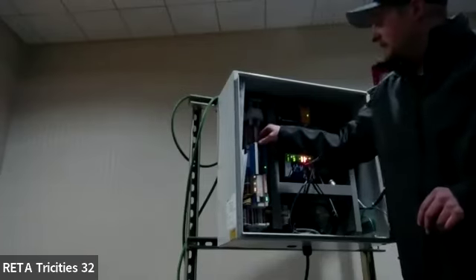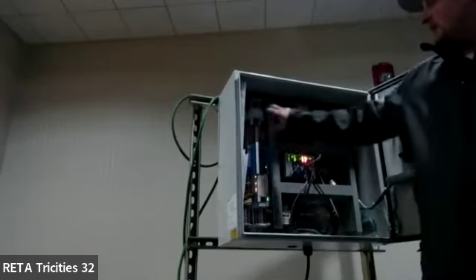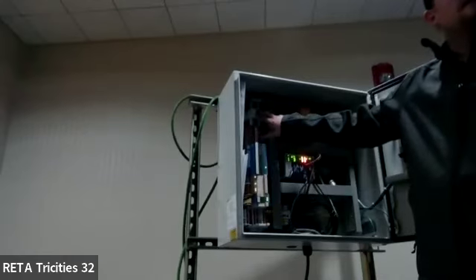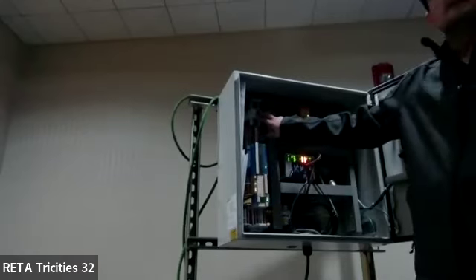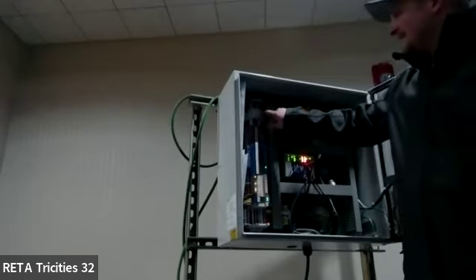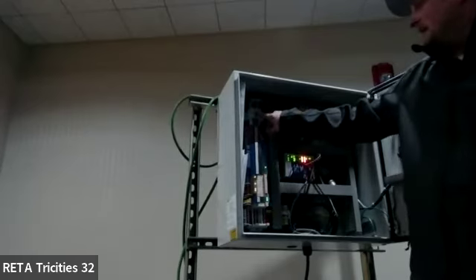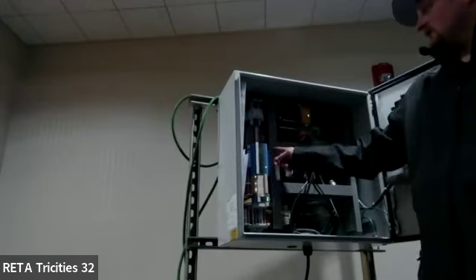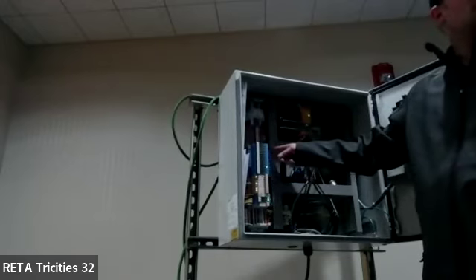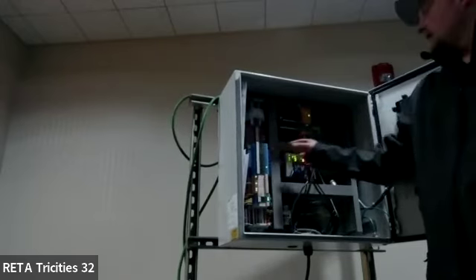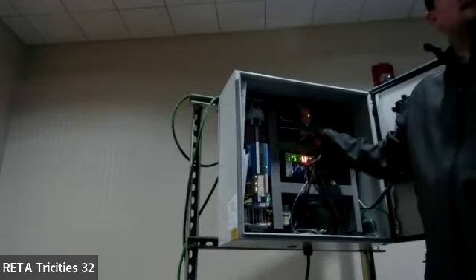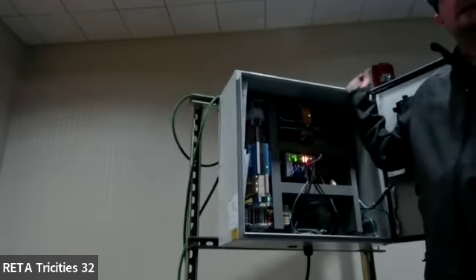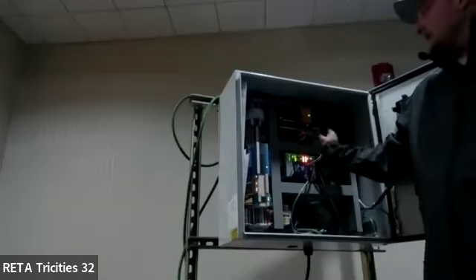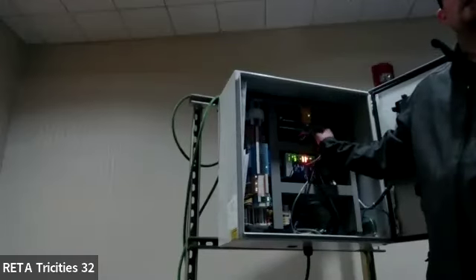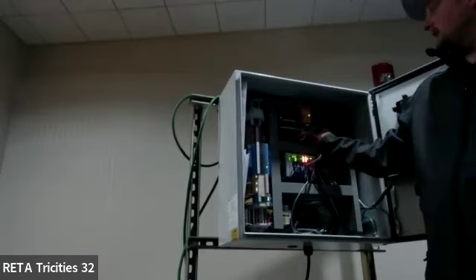Yeah. And this is the contactor for the oil heater. If you wired it wrong and blew it up. The contactor for the oil heater right here. And in most cases, every time I've seen it, somebody put power to this side, the 24 volt side. There's a resettable circuit breaker right here, and it'll explode that. And this green light will turn red. It'll start blinking red, which will indicate that this is toast.